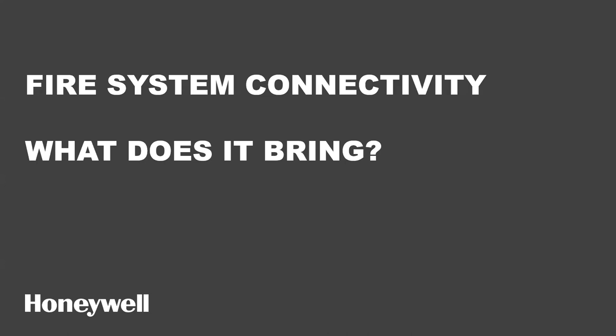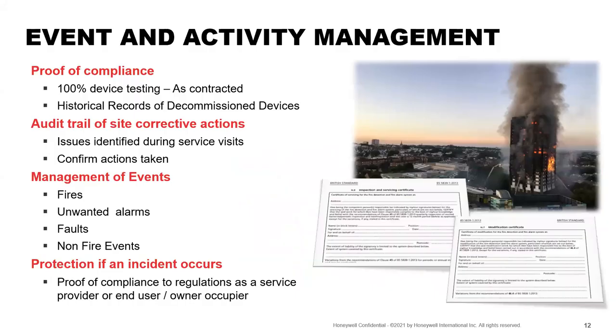Well, fire system connectivity, what does it bring? Well, we're now going to have a look at what it will bring to you guys, well, to all of us, really, that's out there. So in order to ensure that the testing of the system is 100% complete, we need to be looking at the following items, because 100% testing on a fire system is a legal requirement once a year. 100% of the system has to be tested.